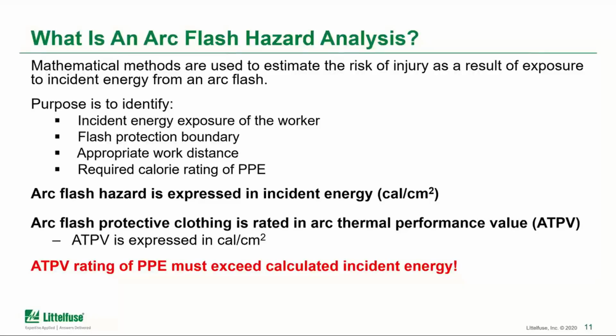And if you continue to drill down, you get to the appropriate work distance. Then you look at the limited approach and the restricted approach boundaries that define what the risk is, what the distances are, and where you need to get your personal protective equipment on. And finally, there's the calorie rating of the PPE. Once you have your hazard analysis complete, you can understand what type of PPE is required to provide that last line of defense in that situation with that equipment. So once you do the mathematical analysis, your arc flash hazard is expressed in the incident energy, and the units there, I've been talking about, are calories per centimeter squared.